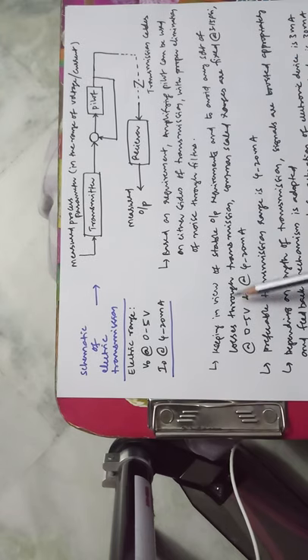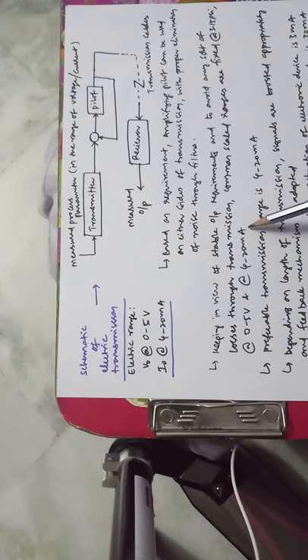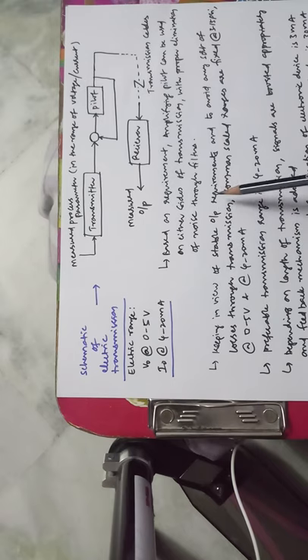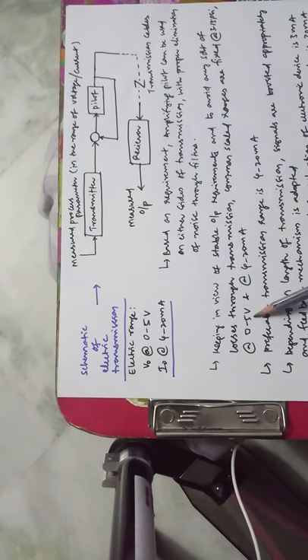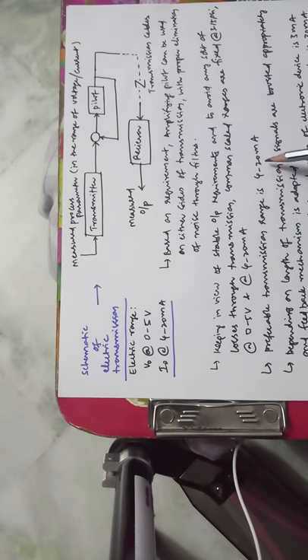Keeping in view the requirements of stable output and avoiding transmission losses, common scale ranges are fixed as: 3 to 15 PSI for pneumatic, 0 to 5 volts for voltage, and 4 to 20 milliamps for current. Any process variable — whether temperature, pressure, density, or others — must be converted to one of these standard ranges.